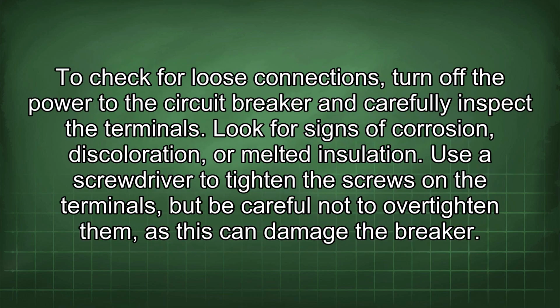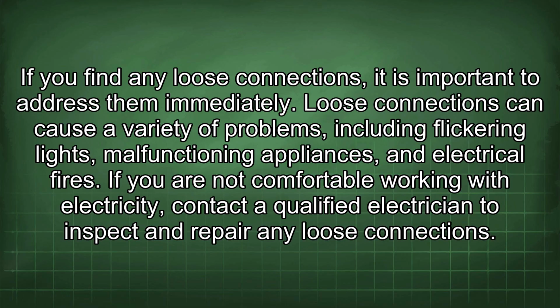To check for loose connections, turn off the power to the circuit breaker and carefully inspect the terminals. Look for signs of corrosion, discoloration, or melted insulation. Use a screwdriver to tighten the screws in the terminals, but be careful not to over-tighten them, as this can damage the breaker. If you find any loose connections, it is important to address them immediately. Loose connections can cause a variety of problems, including flickering lights, malfunctioning appliances, and electrical fires. If you are not comfortable working with electricity, contact a qualified electrician to inspect and repair any loose connections.